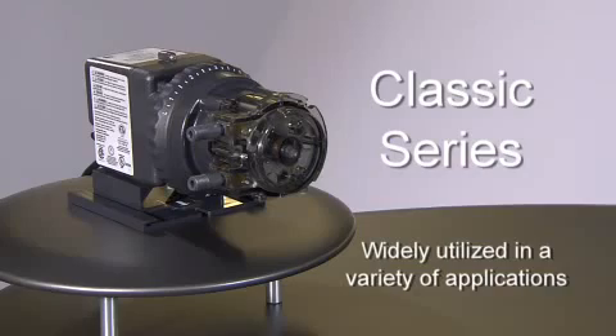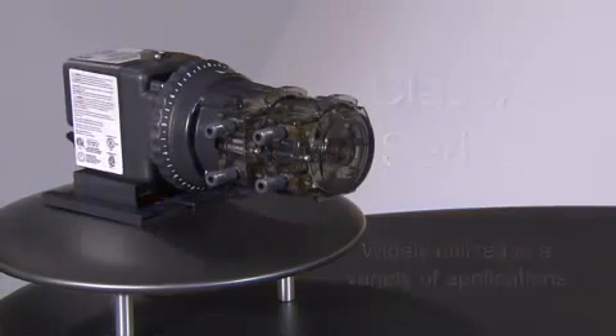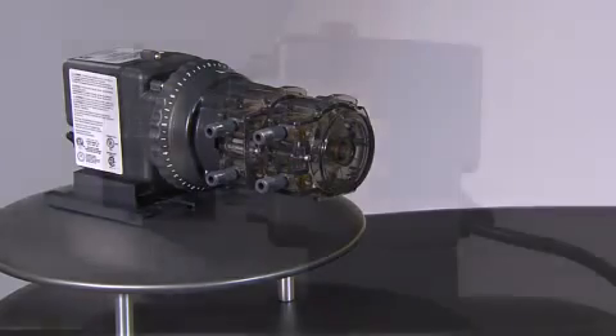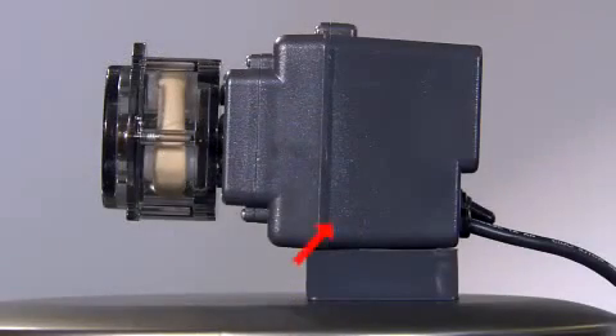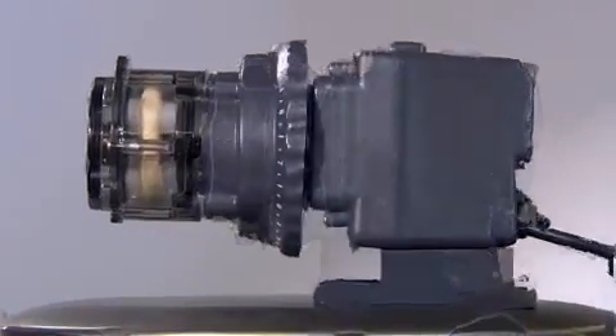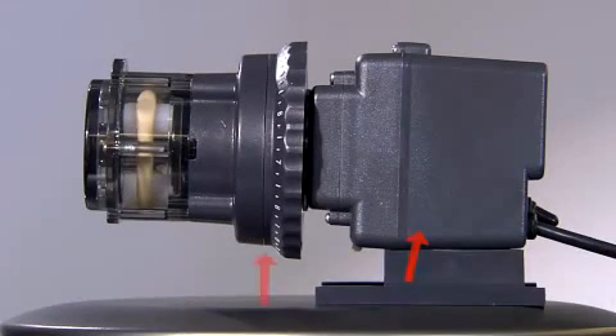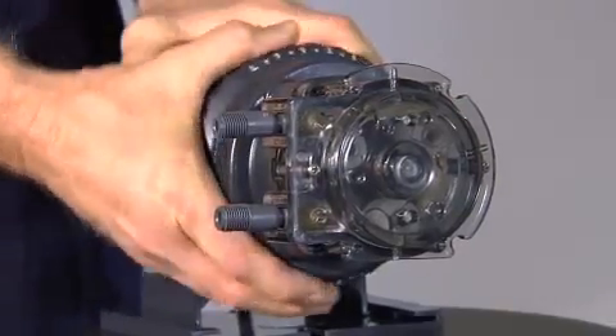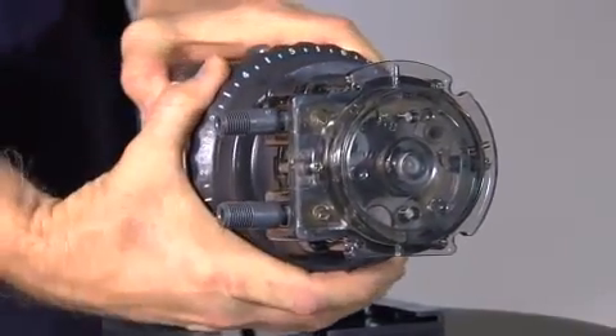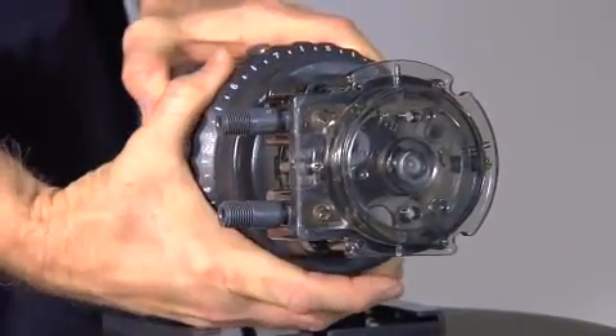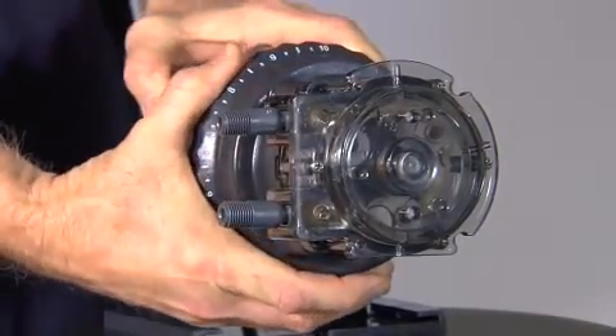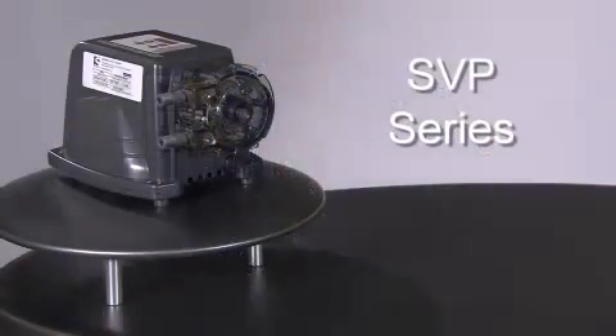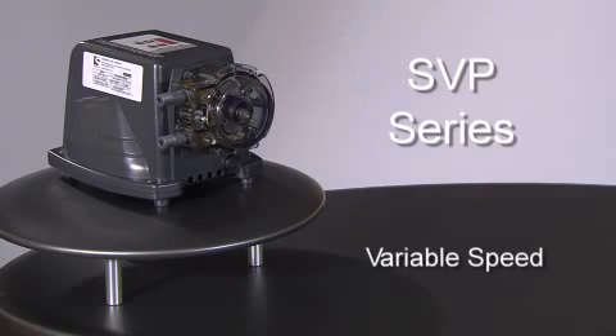The Classic Series is available as a single head or double head, with either an adjustable output or fixed output. The fixed output consists of a motor and the pump head. The adjustable output consists of the motor, feed rate control, and pump head. The feed rate control allows the pump's output to be scaled from 5% to 100% in 2.5% increments by turning the external dial ring.